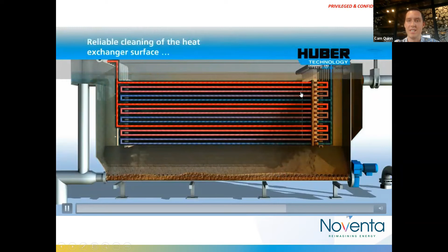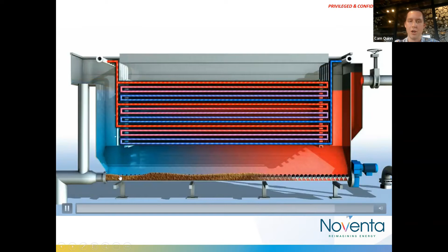So this is a self-cleaning heat exchanger that has a mechanical trolley that scrapes the tubes as frequently as needed. Typically, it's once every day or two. The sediment from the tubes falls to the bottom where there's an additional auger. And on that auger, there's a valve that you can't see here, obviously, that would open up only to discharge the sediment, and it self-cleans.